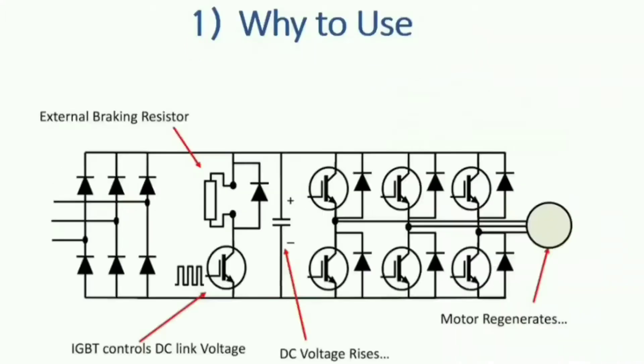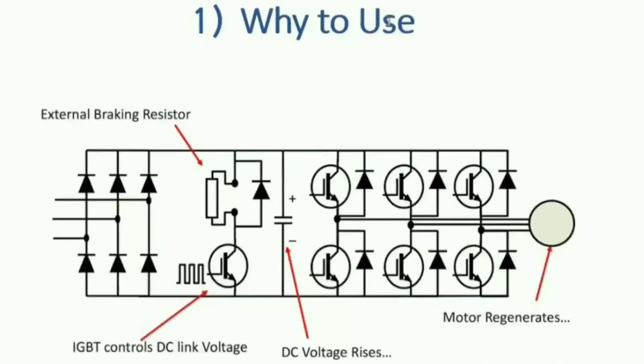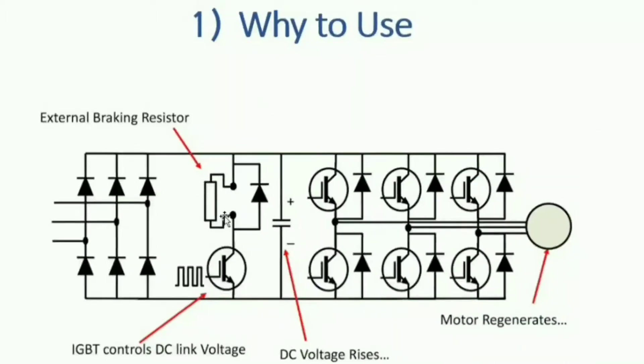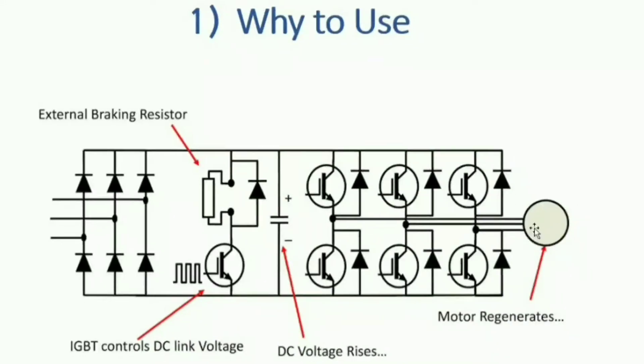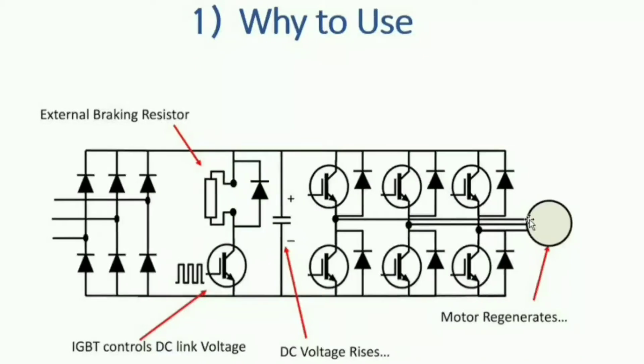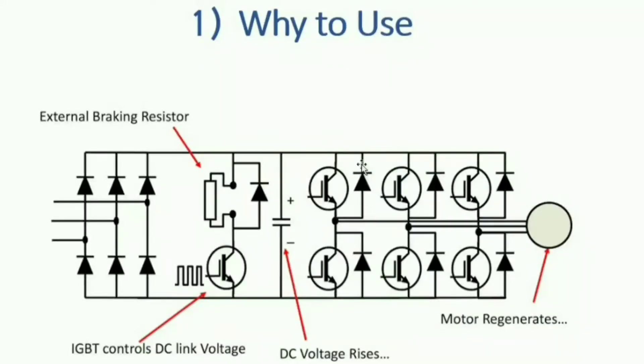First topic: why do we use braking resistors? Whenever we run a motor at say 1500 RPM or 1800 RPM and we suddenly stop the motor, the motor acts as a generator and creates back EMF. If we don't have freewheeling diodes, the IGBT will be damaged. The back EMF goes through the diodes to the capacitor bank and increases the DC voltage.